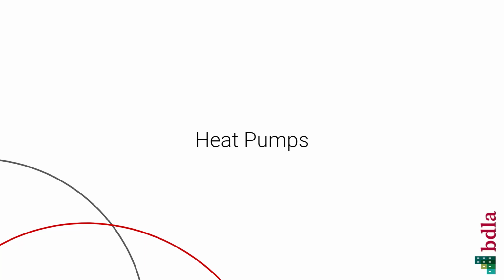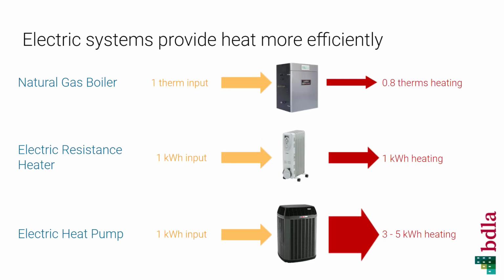The preferred method for electric heating is heat pumps, which is really what we'll dive into for the rest of the video. So why are heat pumps so much better? As we saw, a natural gas boiler is about 80% efficient, so 1 unit of gas in, 0.8 units of heat out. Electric resistance, again, 100% efficient, 1 in, 1 out. A heat pump, on the other hand, can be 300 to 500% efficient. So 1 kilowatt hour of electricity in can produce 3 to 5 kilowatt hours of heating.